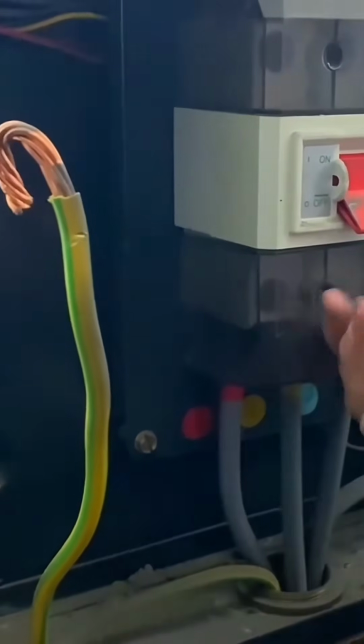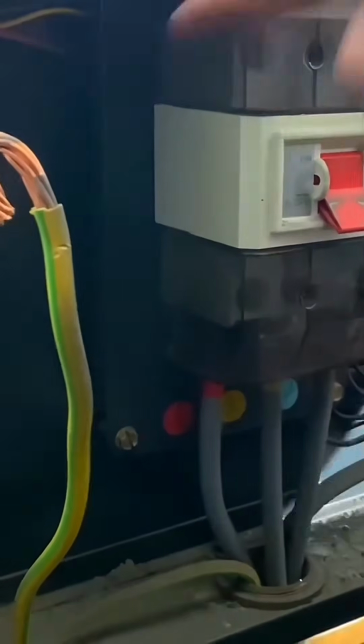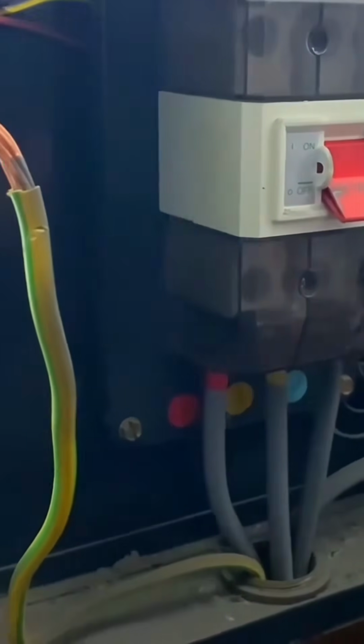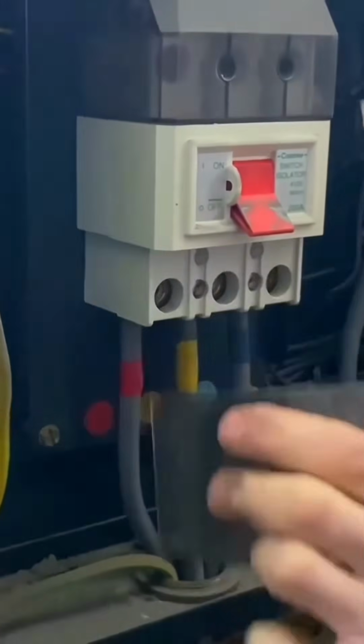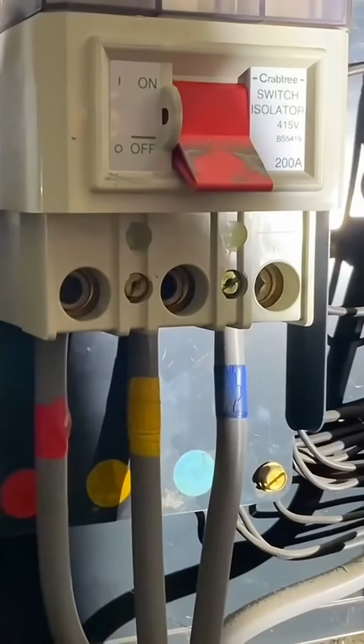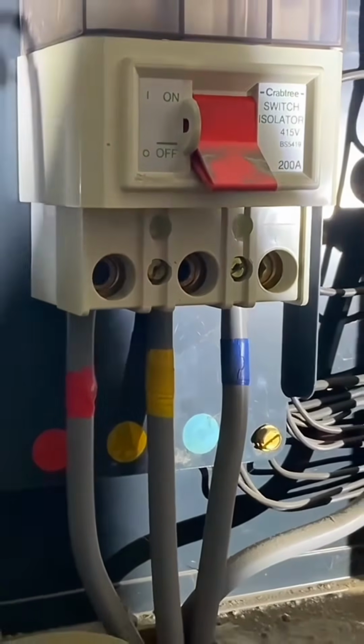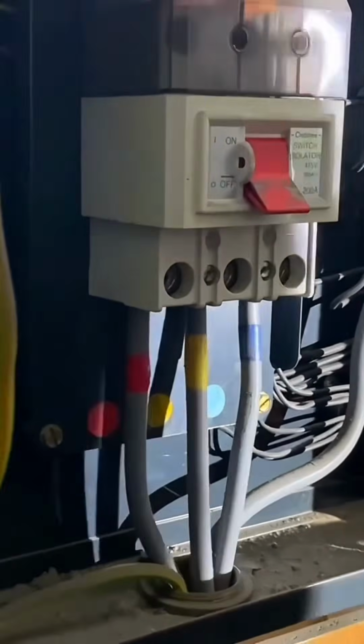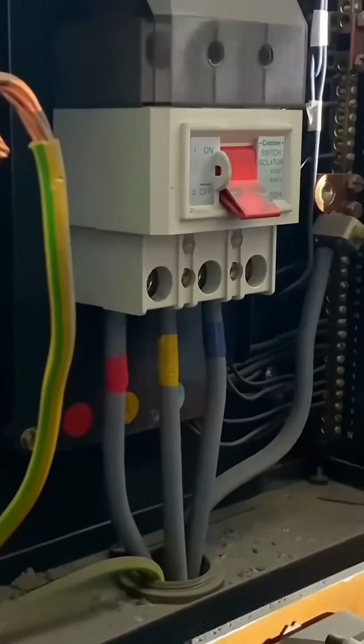Earthing conductor's out. We're just going to drop this off. Right, so yeah, we've got the earth out. Still take care, because obviously the bottom side of this is live, but we're in the real world here, so they're now live at the bottom of that switch. Yeah. And it's red, yellow, blue, and not brown, black, grey. And we're going to set up our instrument now in order to carry out that external earth fault loop impedance.